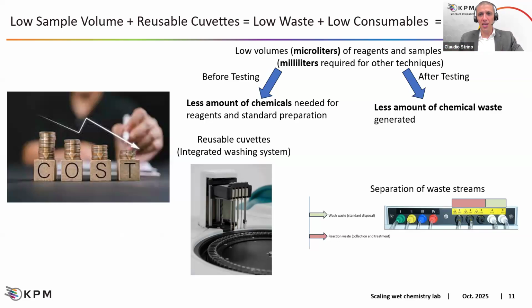Moreover, passing from milliliters to microliters for sample and reagents, because manual or semi-auto techniques work in milliliters, while here we are working in microliters, we can save cost before testing because we need to prepare less amount of chemicals for reagent and standard, and after testing because we have less amount of waste generated by the instrument. Thanks to the reusable cuvettes, and we already saw the washing station, the instrument, all the SmartChems, are only generating liquid waste, and not the hazardous solid waste, because today we are the only brand, only company on the market working with reusable cuvettes.